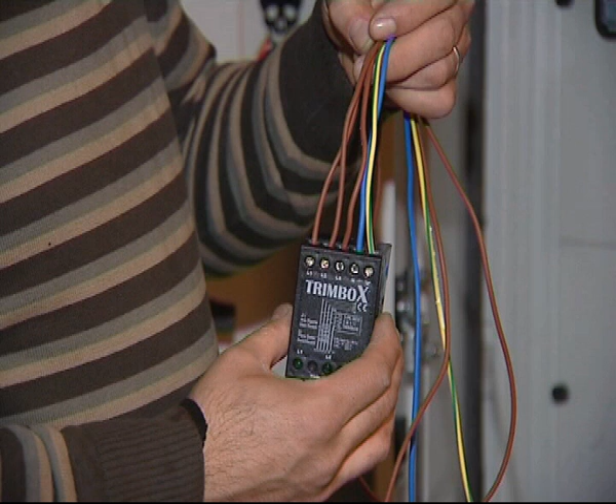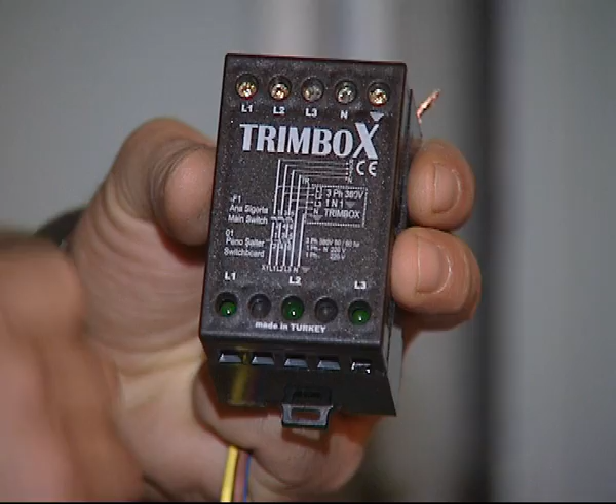For three-phase Trimbox connections, first the energy that feeds the unit is cut. Then one connection for each phase is taken from the outlet of the feeding compact power switch and connected to Trimbox L1, L2, L3 and N. Then earth and neutral connections are made, and the Trimbox is placed on a 35mm rail in the panel.